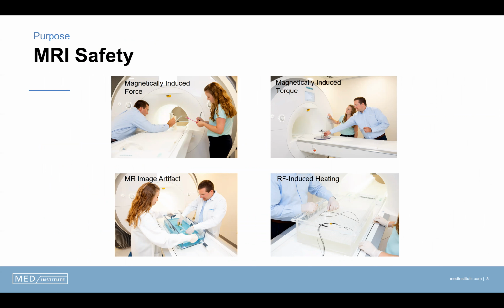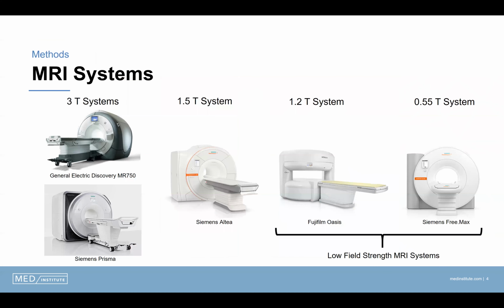For electrically passive devices, especially implants, this evaluation addresses the magnetically induced force, torque, image artifact, and RF-induced heating of the device. The purpose of this research was to evaluate and compare the safety of medical devices in high field and low field MRI systems in terms of these metrics. The 3 Tesla and 1.5 Tesla MRI systems on the left were used to evaluate device safety in higher field MRI systems, whereas the 1.2 Tesla open bore system and the 0.55 T system on the right were used to evaluate device safety in low field MRI systems.